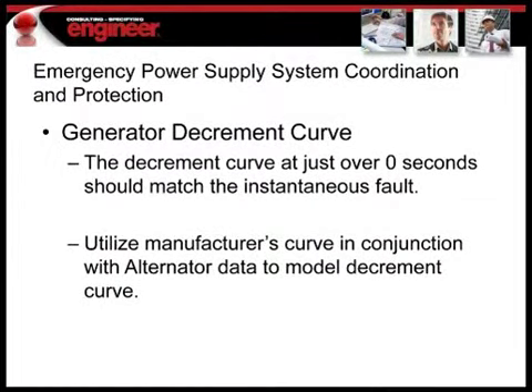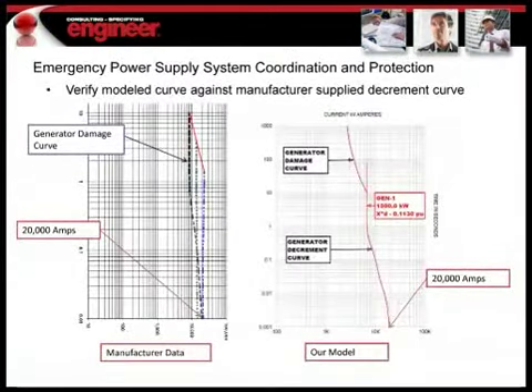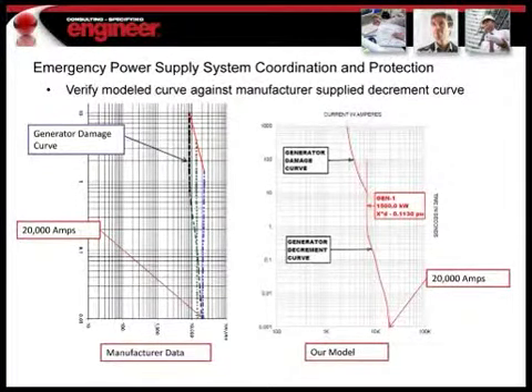So some of the double checks you want to do is you want to make sure the decrement curve matches the instantaneous fault that we calculated. And it's a good idea to take the manufacturer's curve and the modeled curve and put them side by side and take a look and make sure that they match. Here's an example of that. So you can see that we're about 20,000 amps on either the left side, which is the manufacturer's data, and then our model, which is the right side, at the outset. And then you can see how it decays. They're not exactly the right scale, but they're decaying in the same fashion, the same way. So we know our model is good to go.